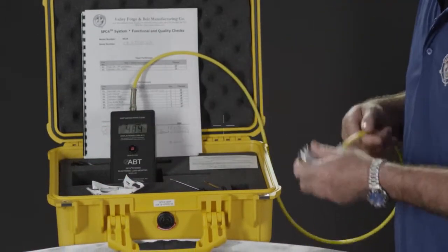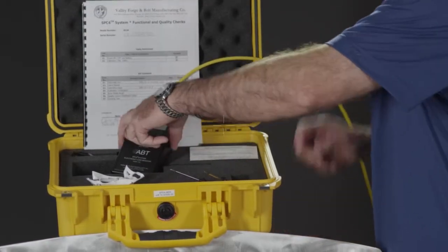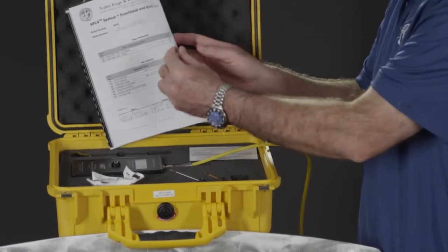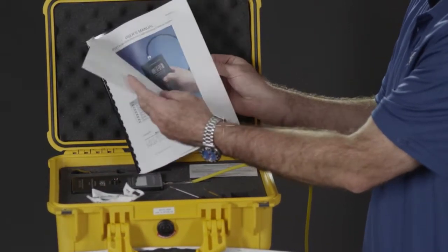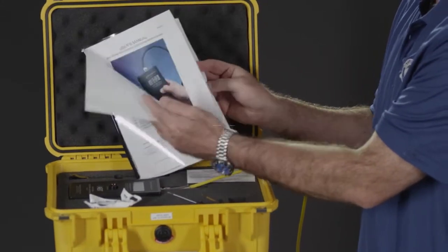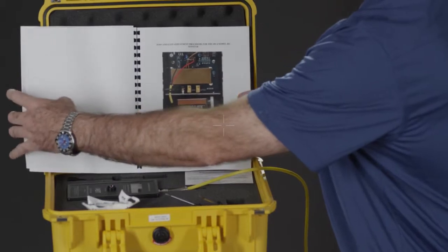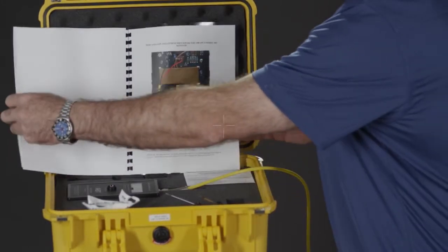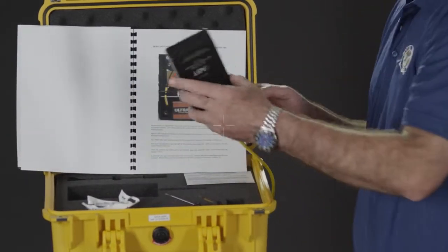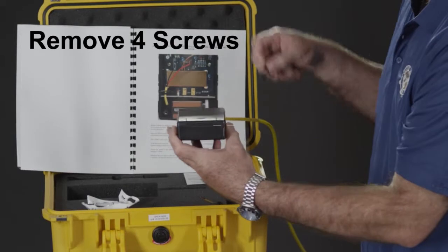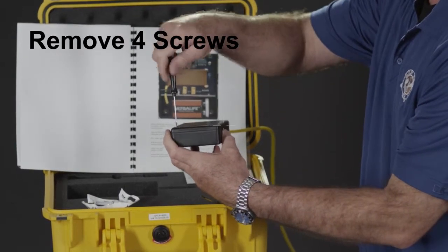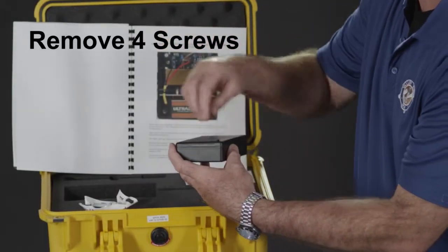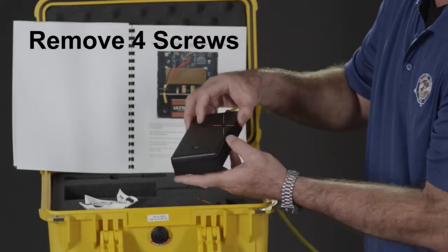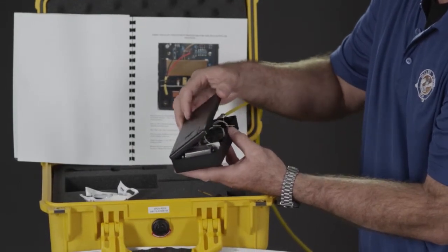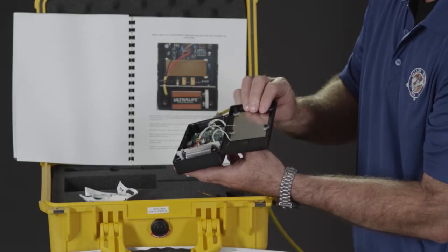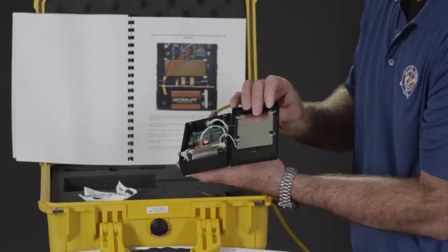So you put the unit down, you can turn it off for a little bit, you turn your instruction manual to the back page, and it covers a lot of different things about the 402 or the 402A. Basically they're the same units with just different tips, and this is how you adjust the 0. And basically it just describes the adjustment. The first thing you need to do is you get a small Phillips screwdriver and you remove all the back screws. I like to keep everything in the box just so I know that it's in a good location. The back is shielded, so it's got a wire that is connecting it to the unit, okay? So once you open that up, you got to be careful of that shielding wire.